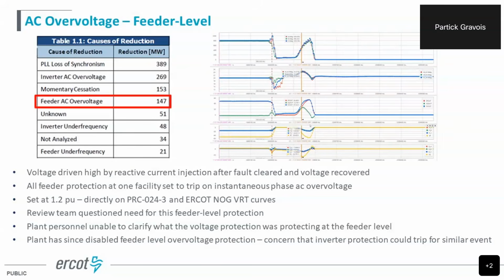So the team, NERC, TRE, and ERCOT, was asking, hey, is this feeder level protection even needed? What are you protecting with this protection? They really couldn't answer that question. They couldn't clarify why that was set that way, only that they saw, hey, there's a 1.2 trip setting, so we probably should trip it there. But that's not the intent of the voltage ride-through curves. It's not a must trip above 1.2. It means you're allowed to trip. So that was something we've really had to stress over the past year.